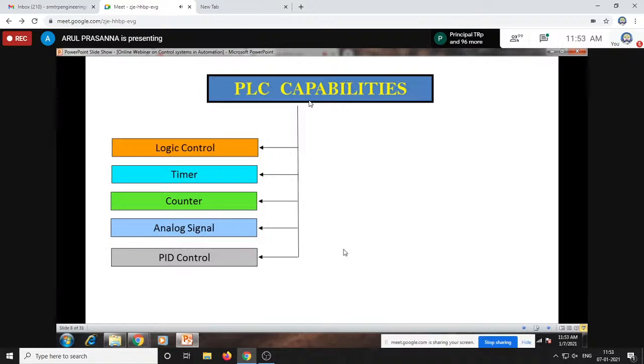Next, it has a PID controller. When you are running a temperature control process, say controlling room temperature with a temperature sensor, you have to use this PID controller. The PID values - KP, KI, and KD - are embedded into the PID controller unit of your PLC, and depending on the variation in temperature, the curves are automatically defined by the PLC's PID controller, maintaining the temperature in a normal settling state.